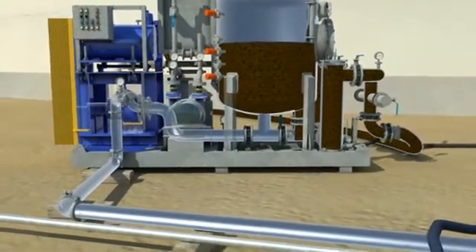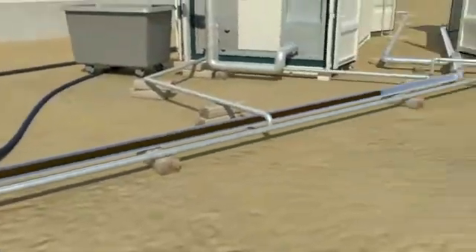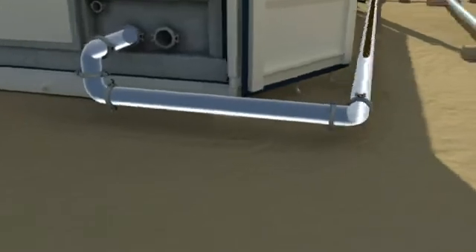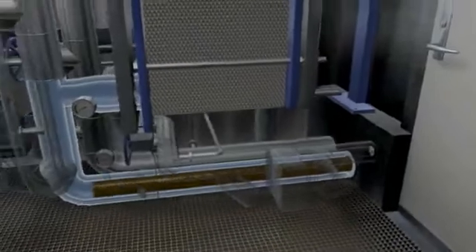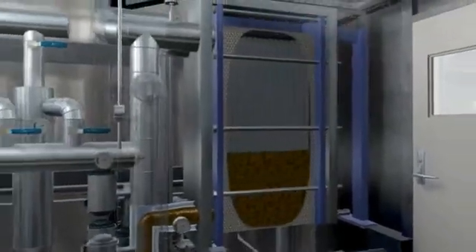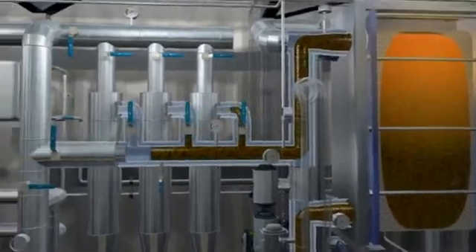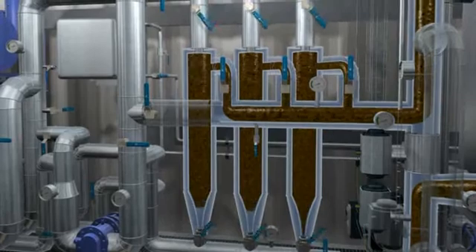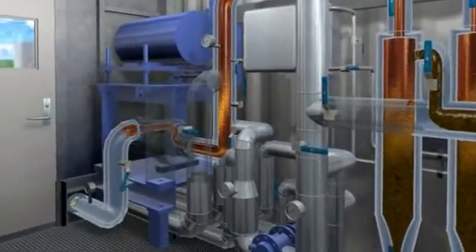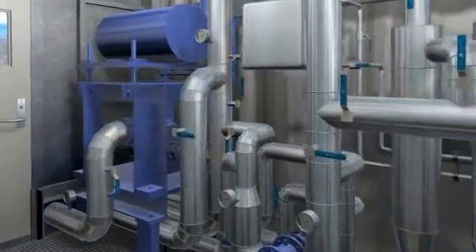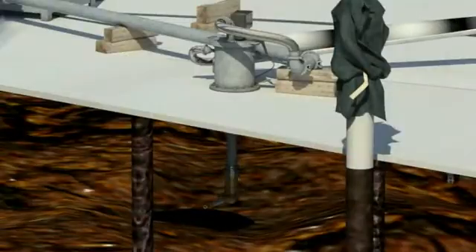In the absence of such gases, the vacuum tank can be bypassed. The oil is pumped onto the recirculation module. If the viscosity is too high, the oil is heated in a plate heat exchanger. From the heat exchanger, the oil is led to the hydrocyclones to separate heavy solid particles from the recirculating cleaning media. A booster pump returns the cleaner fraction to the storage tank, where it is used to reliquify more sludge. The recirculation loop is complete.